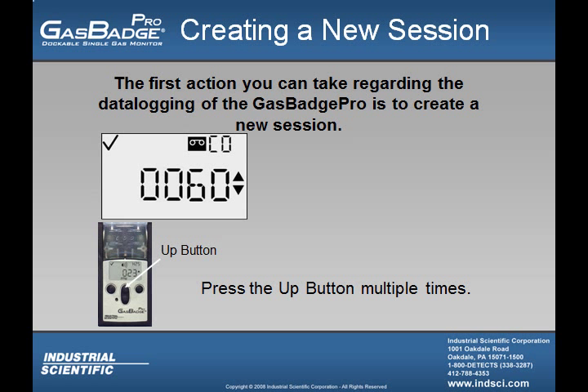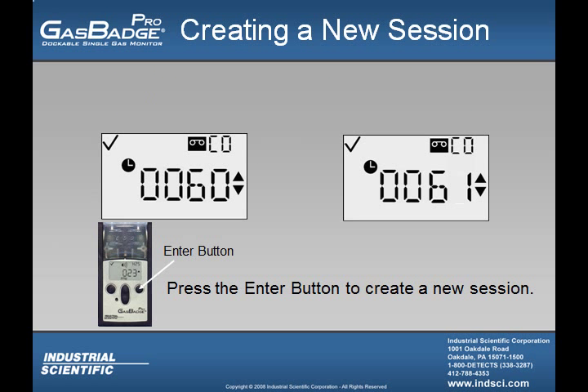The first option the user is able to access is creating a new data logging session. If the user is trying to create a new session, they must press the up button multiple times until they see the tape icon just like the one shown here. Once the user is at the data logging screen, they must press the enter button and they will see the numerical value go up, letting the user know that they have just created a new data logging session.